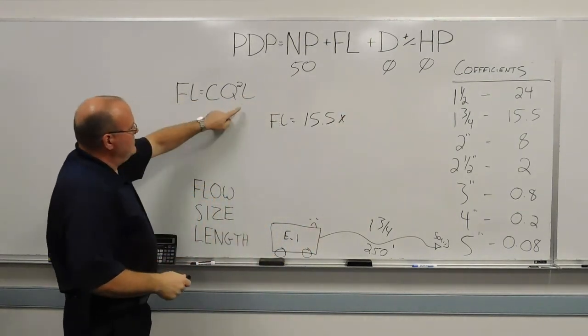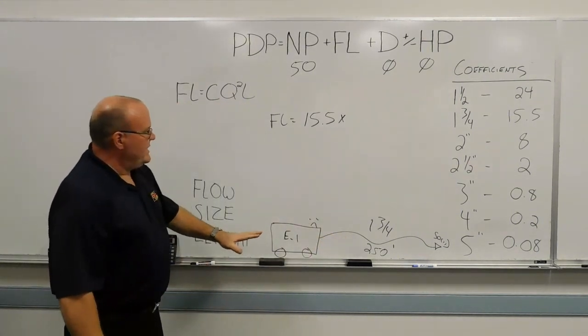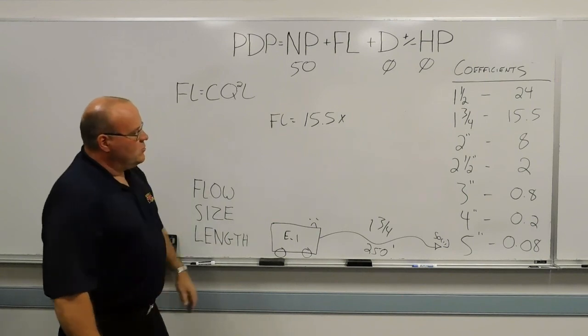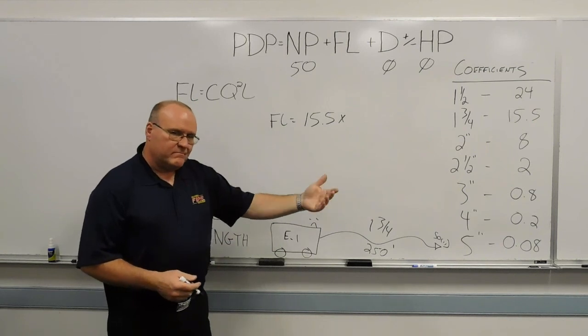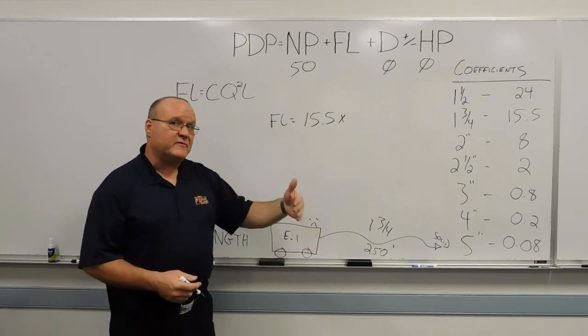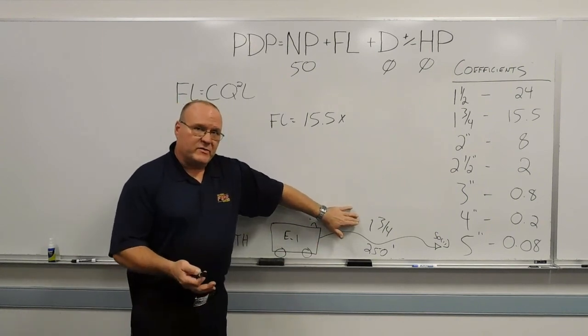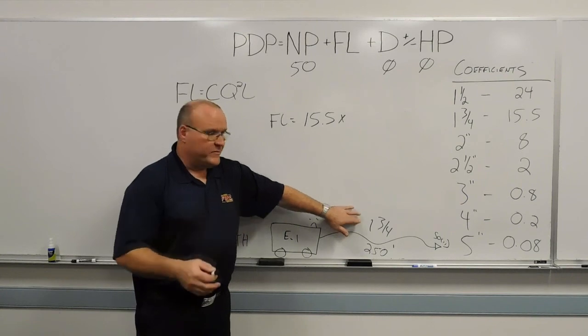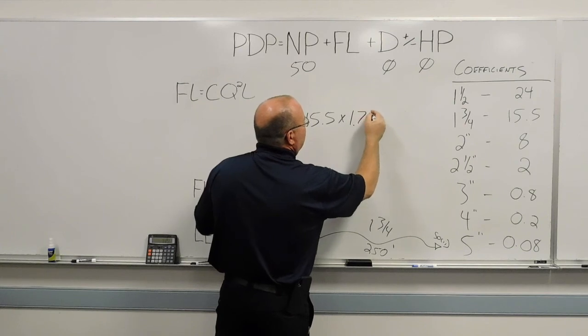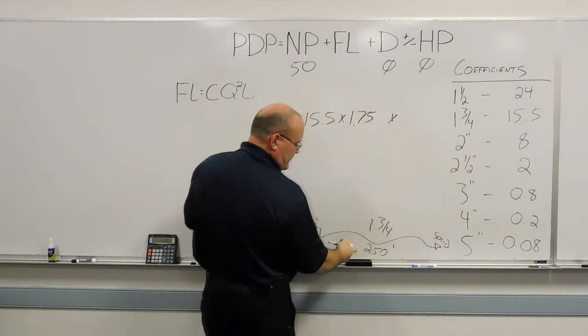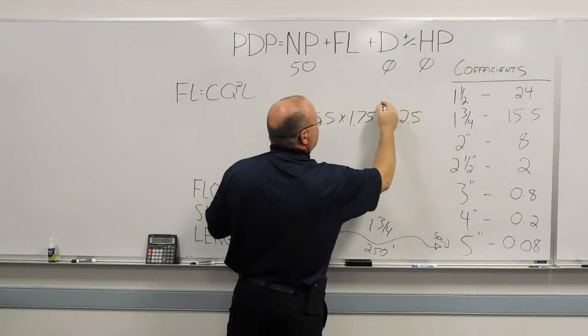And then we know the length of 250 feet. We know what that's going to end up being. We just need to know our flow. So with our inch and three-quarter hose lines, our inch and three-quarter hose line with a solid stream nozzle with a 15/16 tip, we're going to estimate it would be 185 gallons a minute at 50 pounds. We're going to say 175. So 1.75, and we divide that by 100. And then our length, 250 feet divided by 100, 2.5. And this is squared.